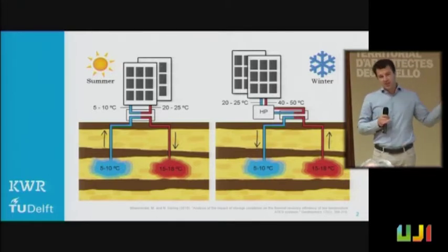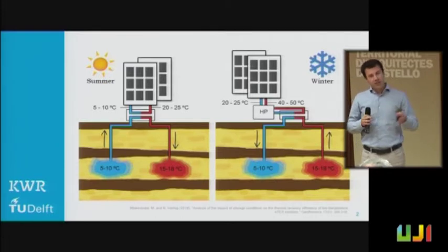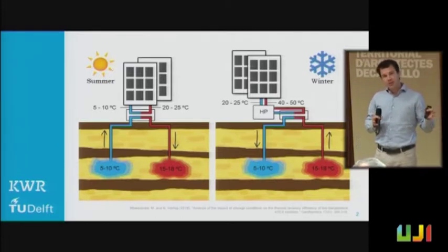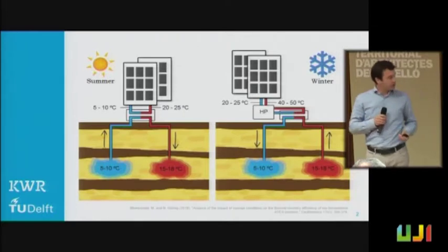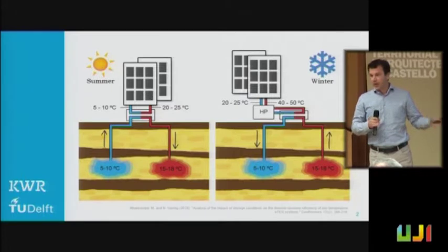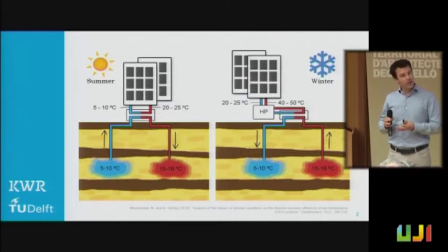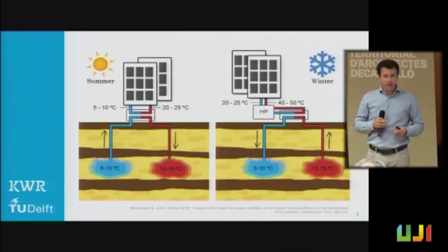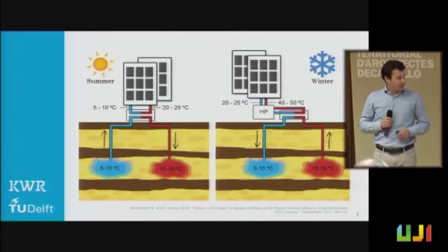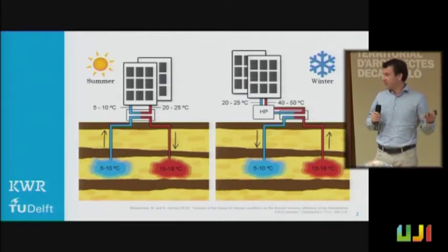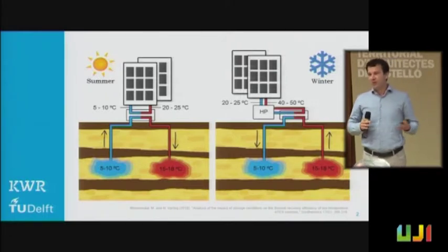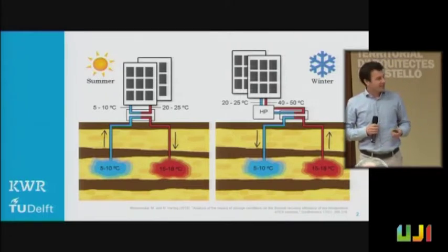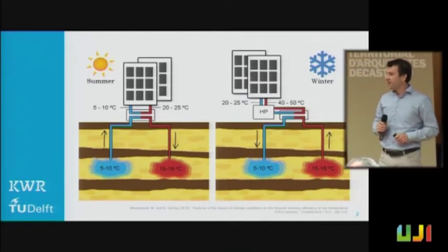So when we want to use this system, the building energy demand profile should balance between heating and cooling demand. We need about as much cooling demand in the building as we need heating demand, because otherwise we're either depleting the cold well after a number of years, or depleting the warm well after a couple of years. But you probably all know or may expect that there's no building that has an exactly balanced heating and cooling demand.